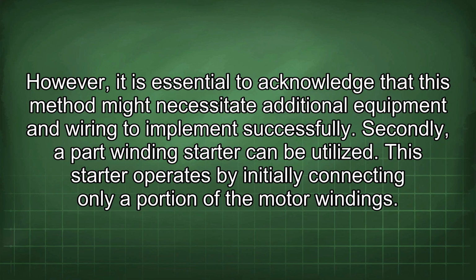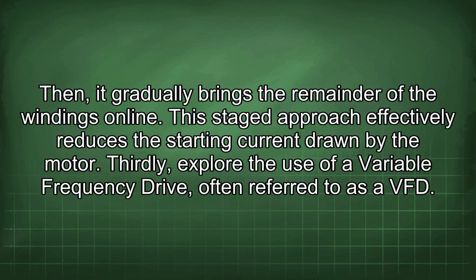Secondly, a part-winding starter can be utilized. This starter operates by initially connecting only a portion of the motor windings. Then, it gradually brings the remainder of the windings online. This staged approach effectively reduces the starting current drawn by the motor.